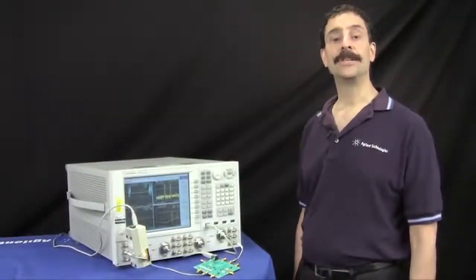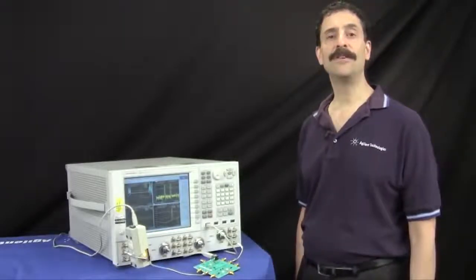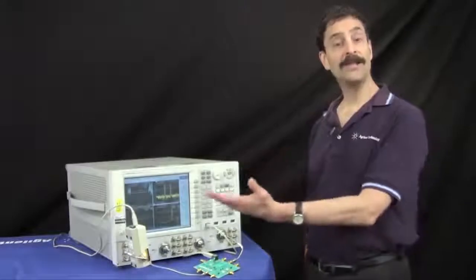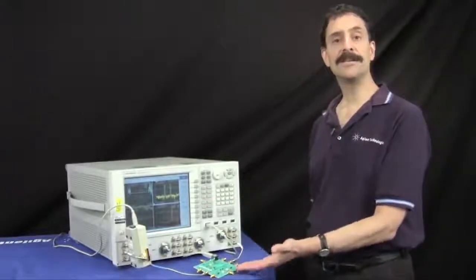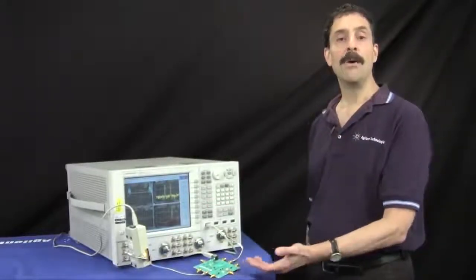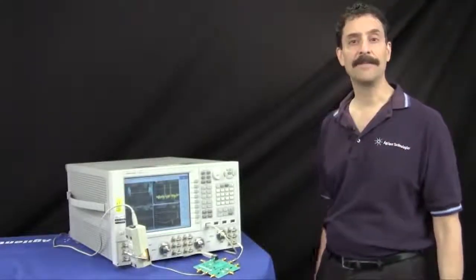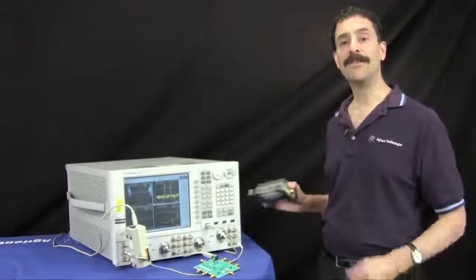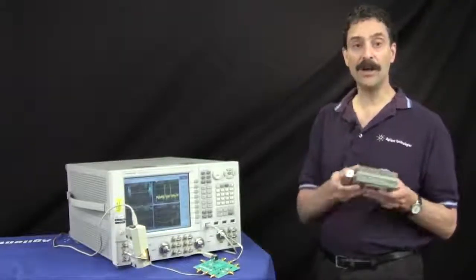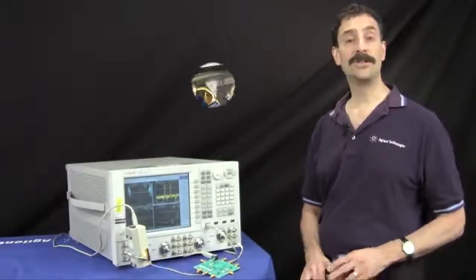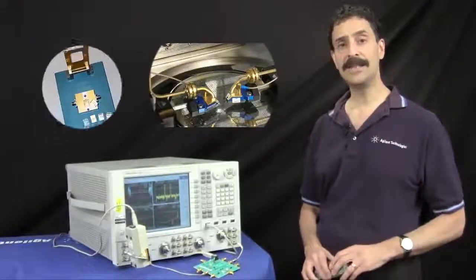The PNA-X uses a different method to measure noise figure. This method maintains the ability to make a broad range of measurements with a single set of connections to the DUT, while providing the industry's highest noise figure measurement accuracy. This accuracy applies for devices with coaxial or waveguide connectors, as well as for devices that are still on the wafer or in test fixtures.